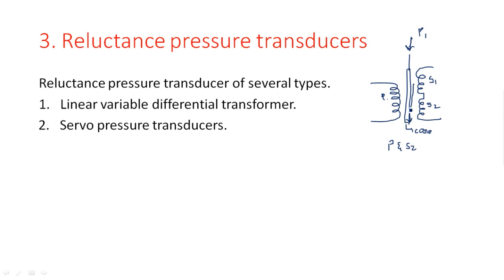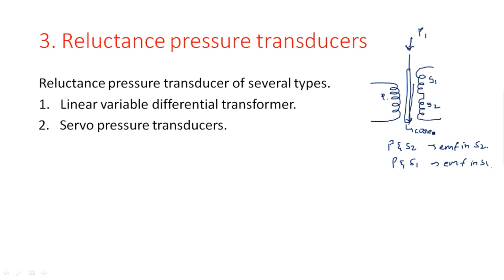Because of this core position, secondary winding 2 will have a lot of EMF generated, because the core comes in between the primary winding and secondary winding 2. If pressure is applied in the reverse direction, the core goes upward and comes in between the primary winding and secondary winding 1, and then EMF is developed in S1.